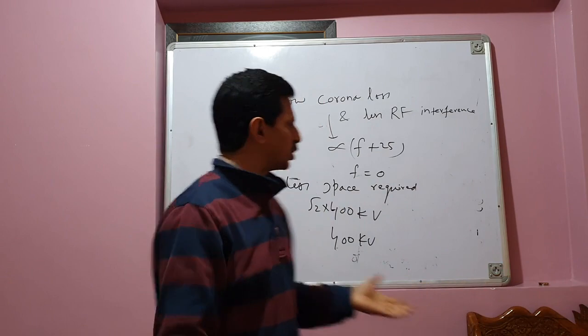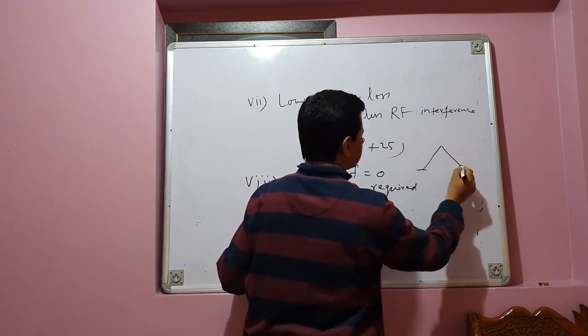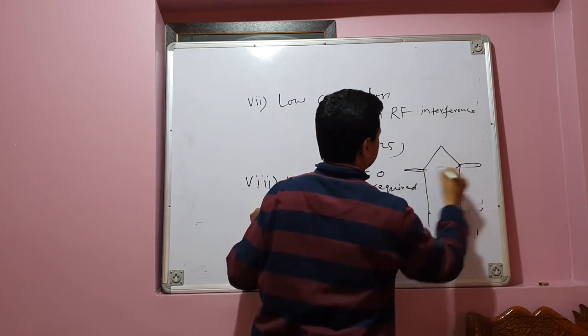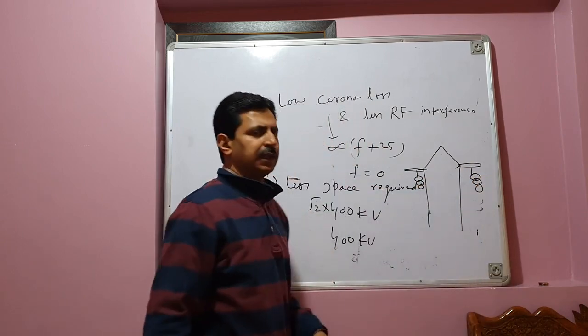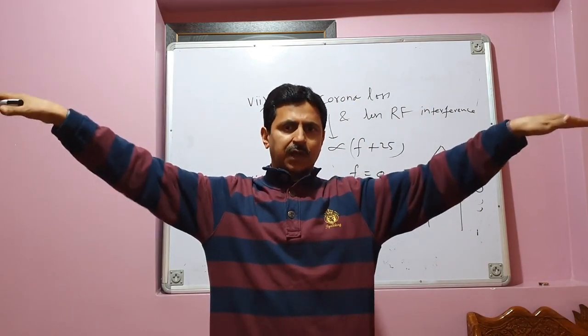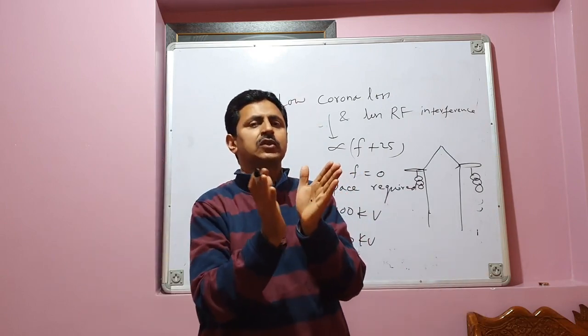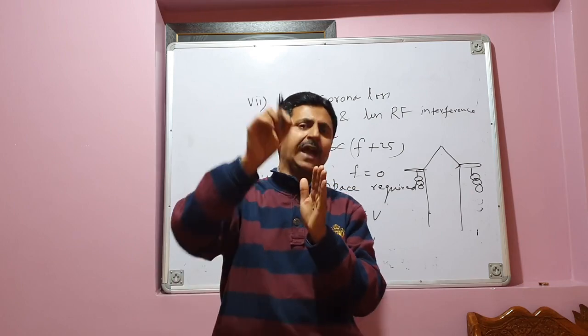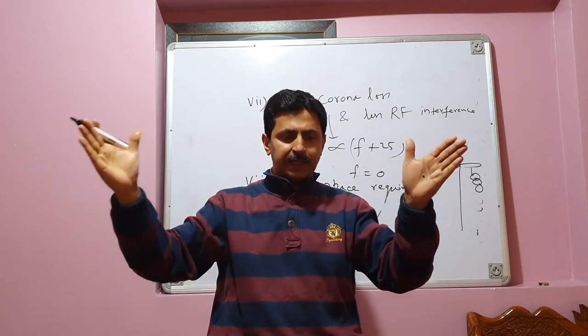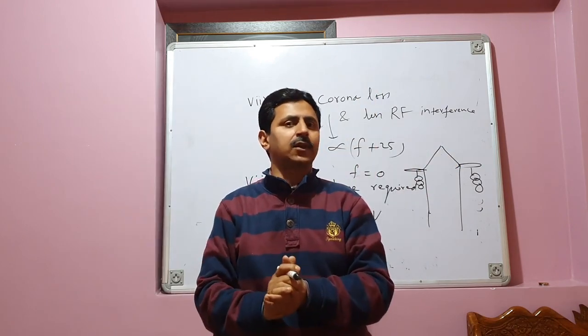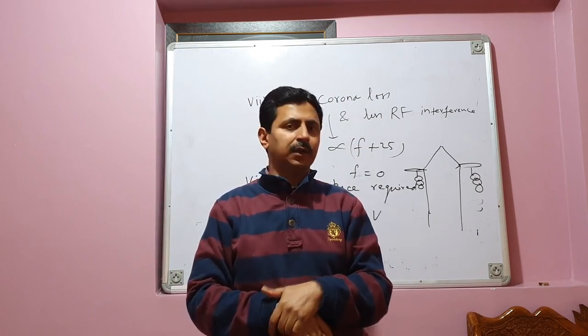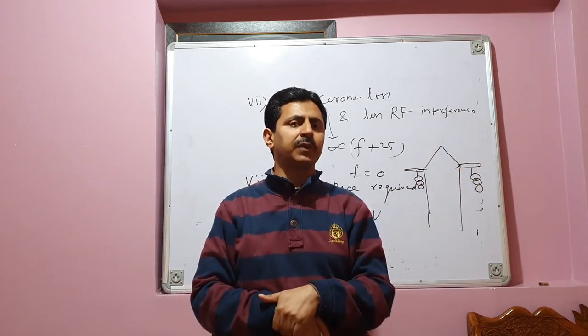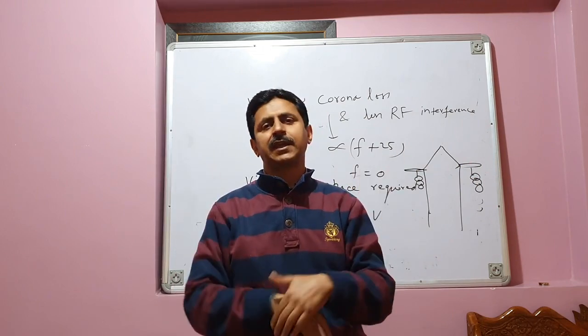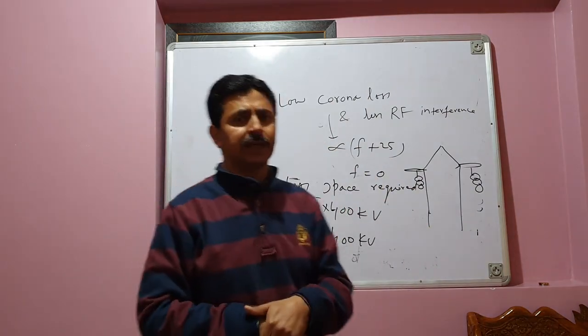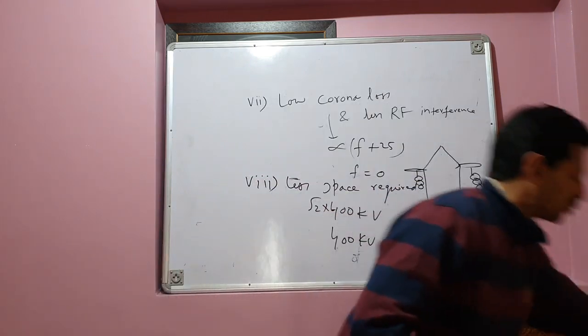And the tower is also smaller. See, this is the transmission tower. This is just a schematic, and these are the insulators. The height, the width, and the length of the cross arms on which you are hanging your insulators is small, because you have to design your insulators for 400 kV or for X kV, not for √2 times X kV. So that decreases the spacing required between the cross arms, and that decreases the overall size of the power transmission tower. So if you happen to see this HVDC transmission tower and compare it with the size of an AC transmission tower, the HVDC power transmission tower is smaller in size than the AC transmission tower. That's what I have written here. Less space is required for HVDC transmission system. So this was the 8th point, which goes in favor of HVDC transmission system.